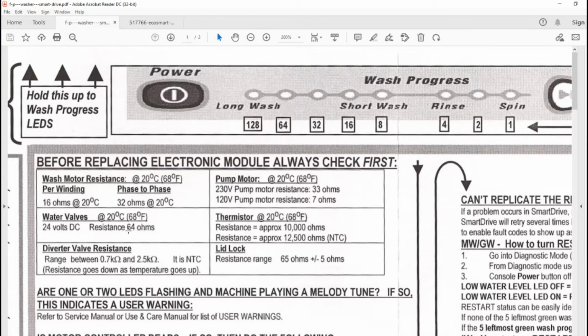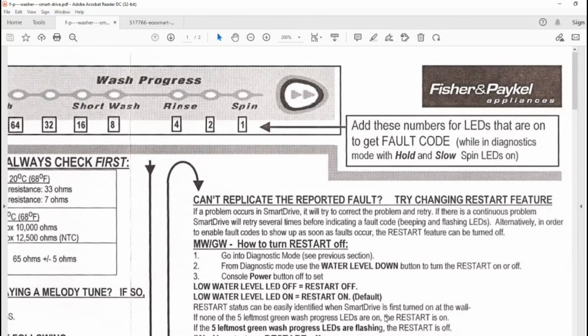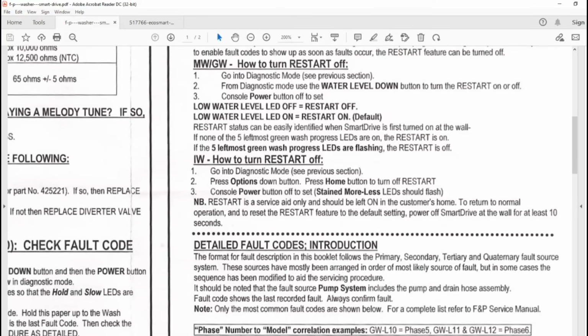I have had some which will fill up the whole bowl full of water and then just finally overheat, the last few centimeters it's filling up. So its resistance is not such a big indication on the water valves until they go open circuit. Then you know you've got a problem.